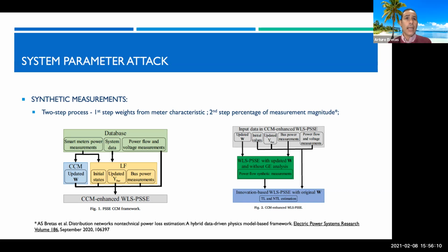So that being said, we started investigating how one could improve these solutions through a simple and not costly approach. And one way that we investigated is what we call synthetic measurements. You should not confuse these with pseudo measurements. These are measurements that are created in the state estimation process. They're not based on historical data. They're created in the state estimator process with the overall idea to increase, if you will, redundancy artificially at certain regions or areas of the system towards improving CPS security.